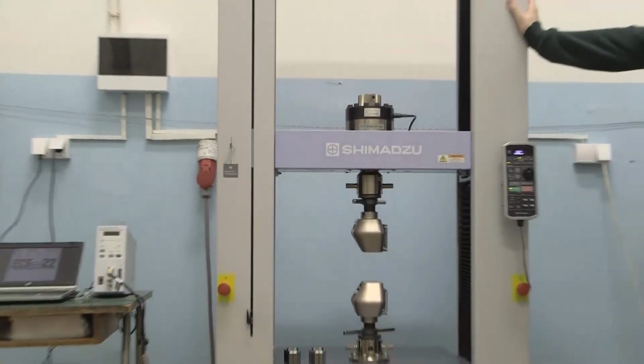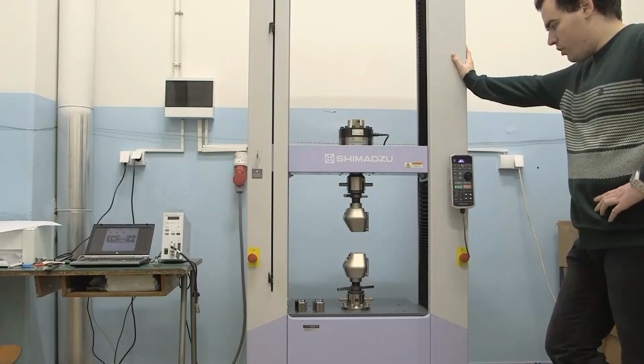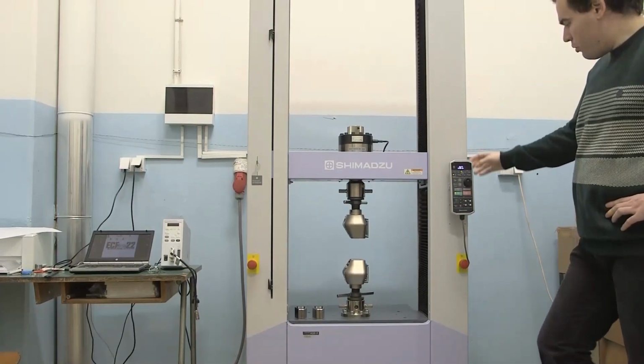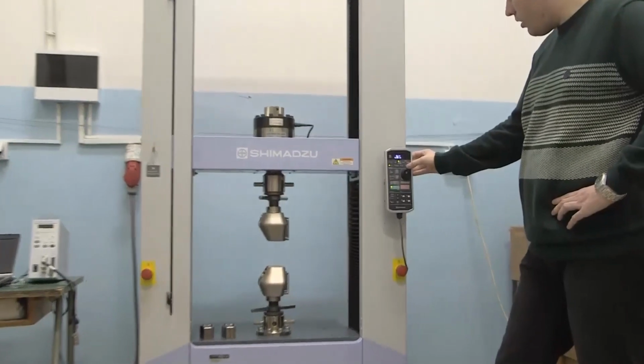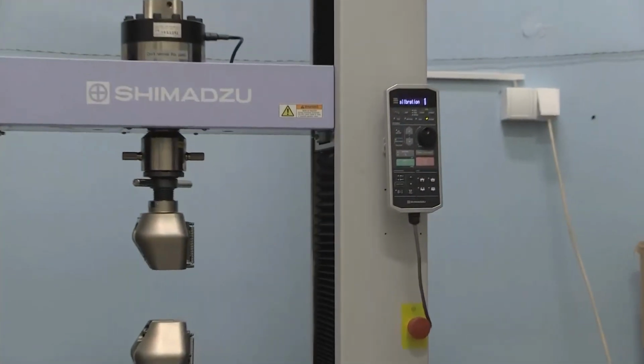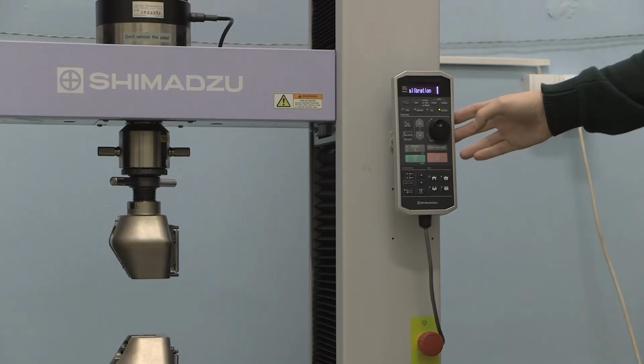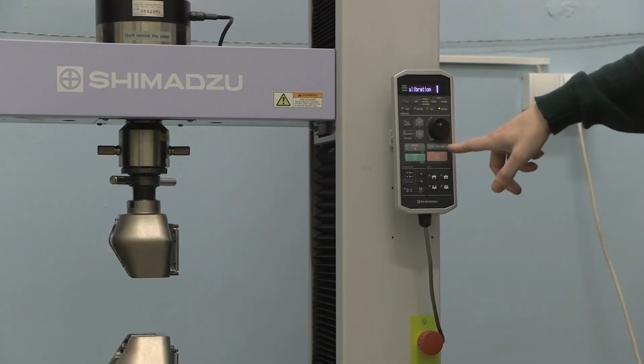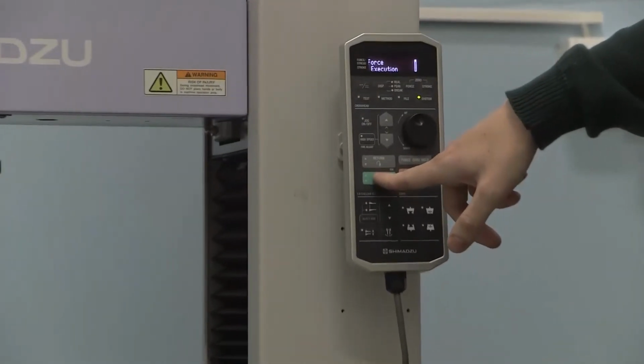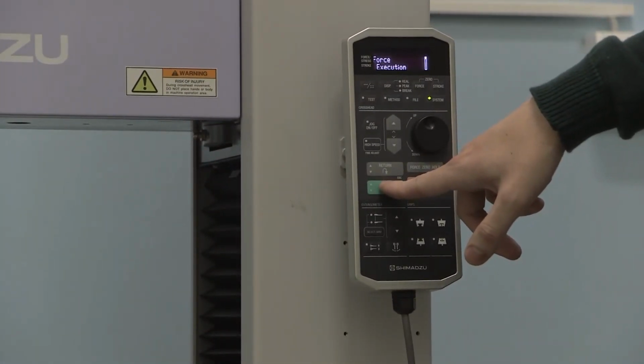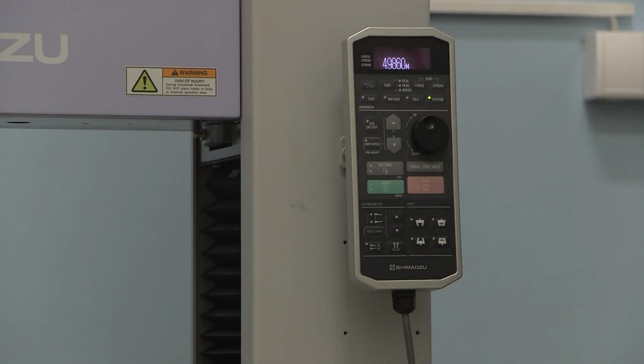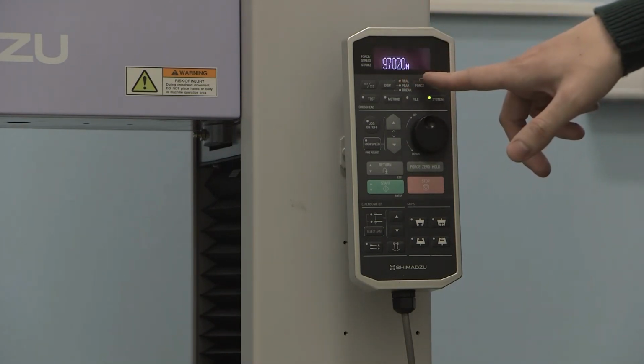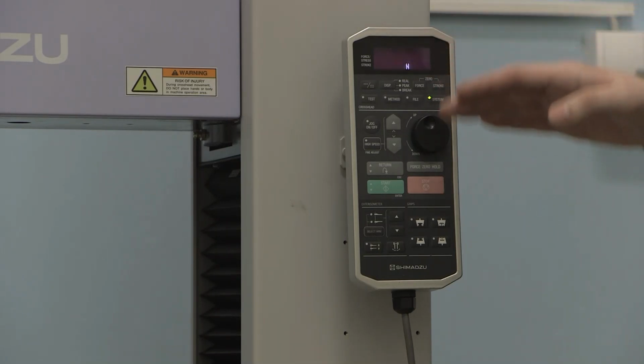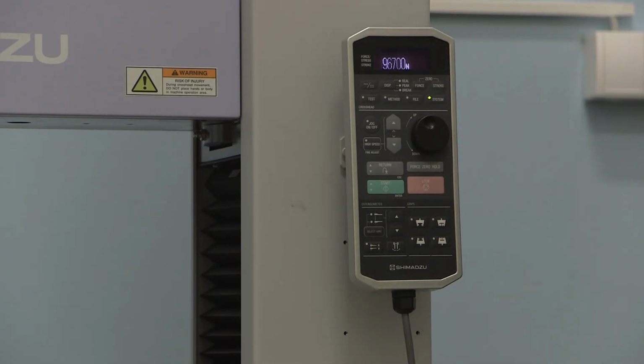First, after switching on your device, you have to click on System to calibrate the machine. Here the machine asks us to calibrate the device. So I'm pressing Start. It will calibrate force in a short while. I'm pressing Start again. And now it performs calibration of force. The force goes to the maximum value and slowly decreases to 0. That's when the calibration will stop.